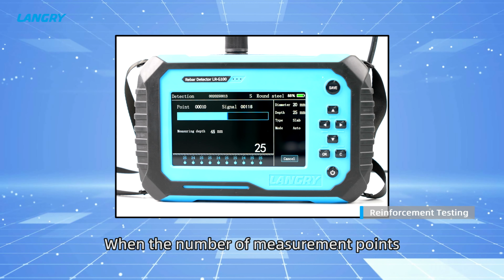When the number of measurement points exceeds the range displayed on the screen, it will automatically flip pages. If you want to estimate the diameter of the steel bar, you need to move the probe directly above the steel bar, press the up arrow key, and the instrument interface will display the estimated diameter value and estimated protective layer thickness value. Press the left and right arrow keys to switch between manual or automatic storage mode. In manual mode, press the save key briefly to store the current thickness value for judgment. Press the down arrow key, and the instrument self-calibrates. Press the C key, select whether to save the data, and then exit the scanning interface.